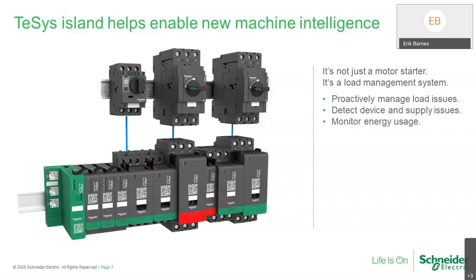So you're going to be able to actively set and monitor for certain issues that your load, your devices downstream, may have. You're going to get alarms about the devices themselves. For example, let's say the contactor is near the end of its usable life. Once it gets to 90% of its usable life, it's going to give you an alarm. That's very convenient, because now I can plan on maintenance. Let's say the breaker device upstream trips, the TeSys Island starter unit is going to give you an alarm saying, hey, your upstream device is tripped.